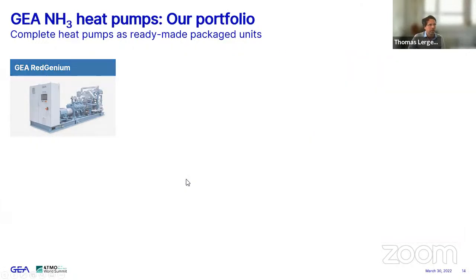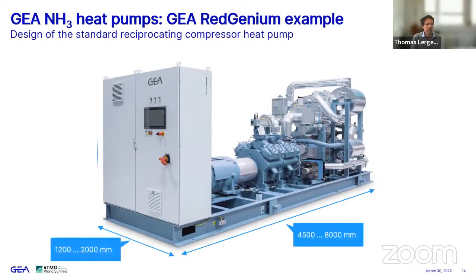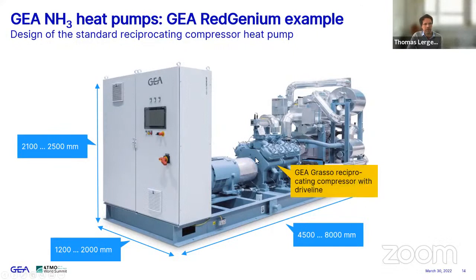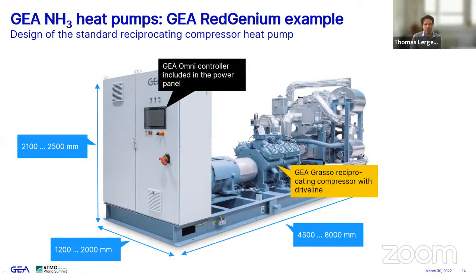Let's have a look at the RedGenium a little bit closer, and to give you an idea of the dimension of how this actually looks like if this was standing in front of you, or if you would be standing next to it. So it's between 4.5 and 8 meters long. It's 1.2 meters wide and a little taller than typical human beings. You see here in the middle, this is a reciprocating compressor, I believe with 8 cylinders here. And there's a driveline included, of course. Then it's completed with our GEA Omni controller included in the power panel. So this is completely fixed and ready to start.